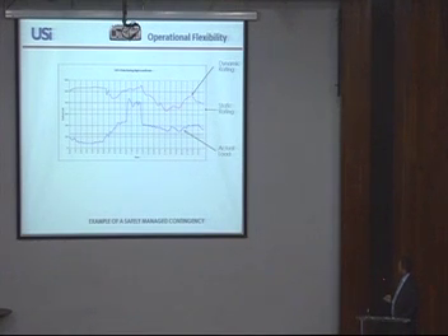So what you can see on this 24-hour plot is that at 10 o'clock in the morning, there was something happening, a contingency, and the current went up and even went above the static rating. For an operator, that means when the current goes up to the static rating, he has to redispatch, he has to react. In that case, he was looking at what is the real capacity of the line.